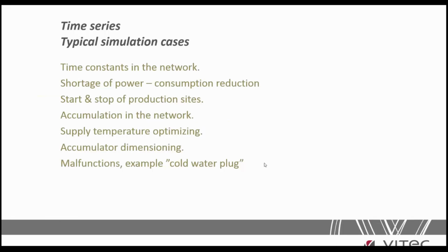If we want to accumulate power in the network, at what time should I start a plant or raise the temperature to have the hot water at the substations in the morning? Dimensioning of accumulators. Well, if the accumulator is located in the middle of town and you have plants in the suburbs, maybe you can get some information from this kind of simulation.